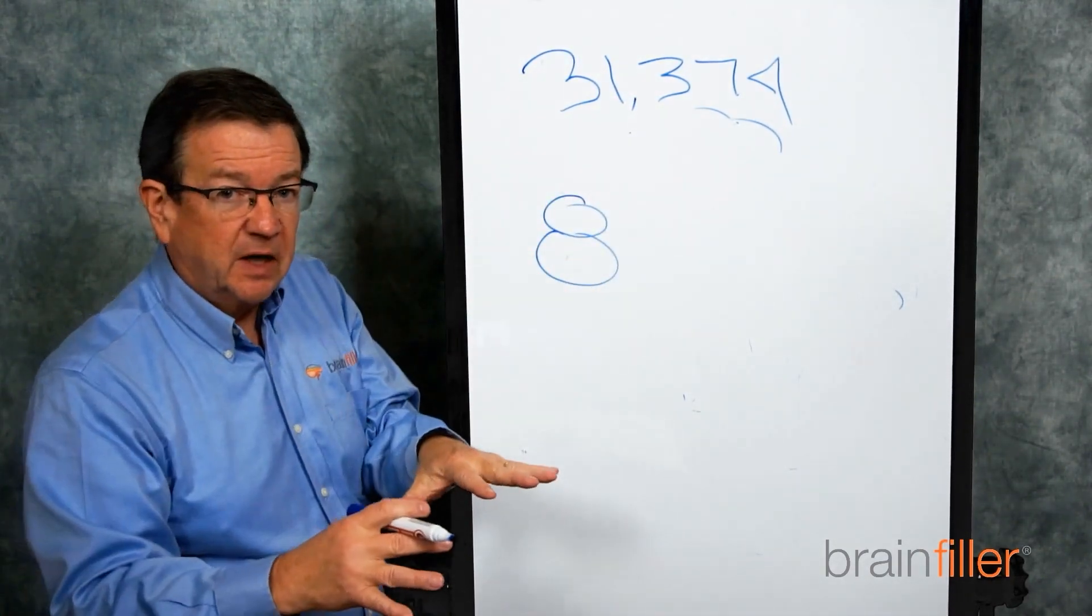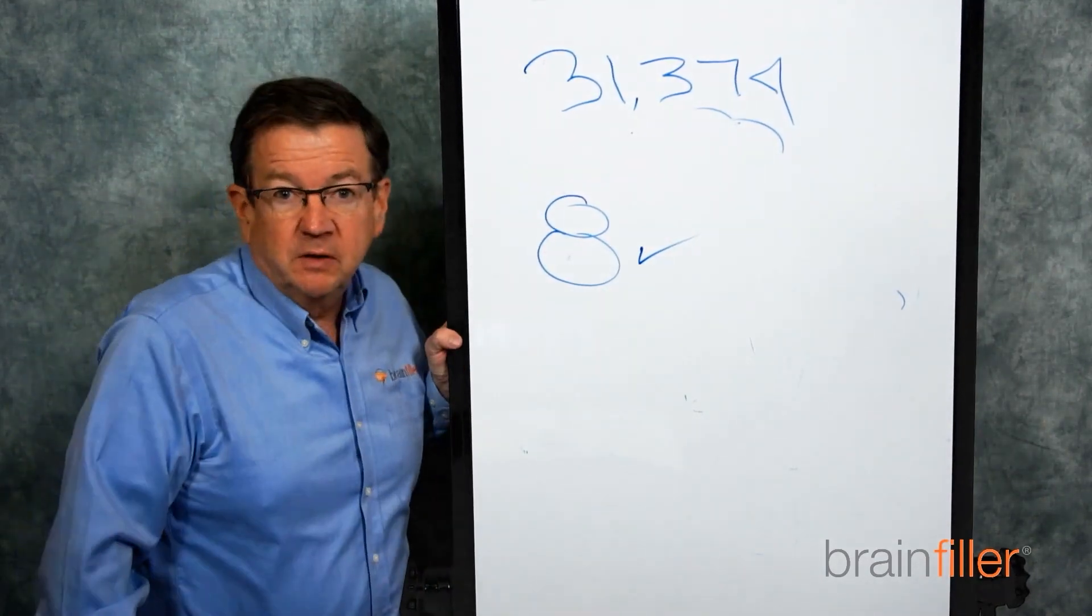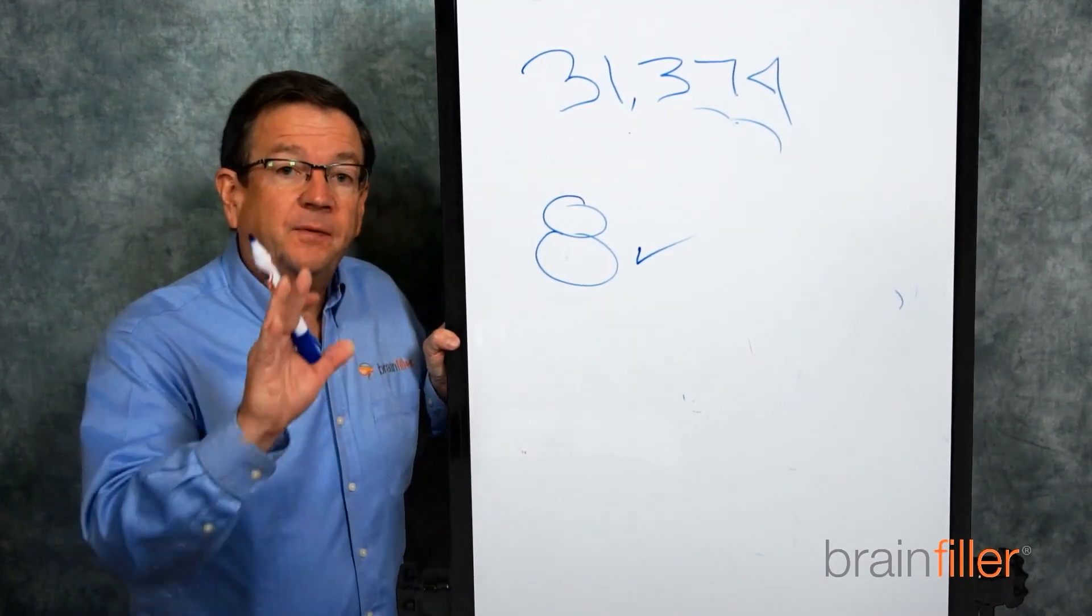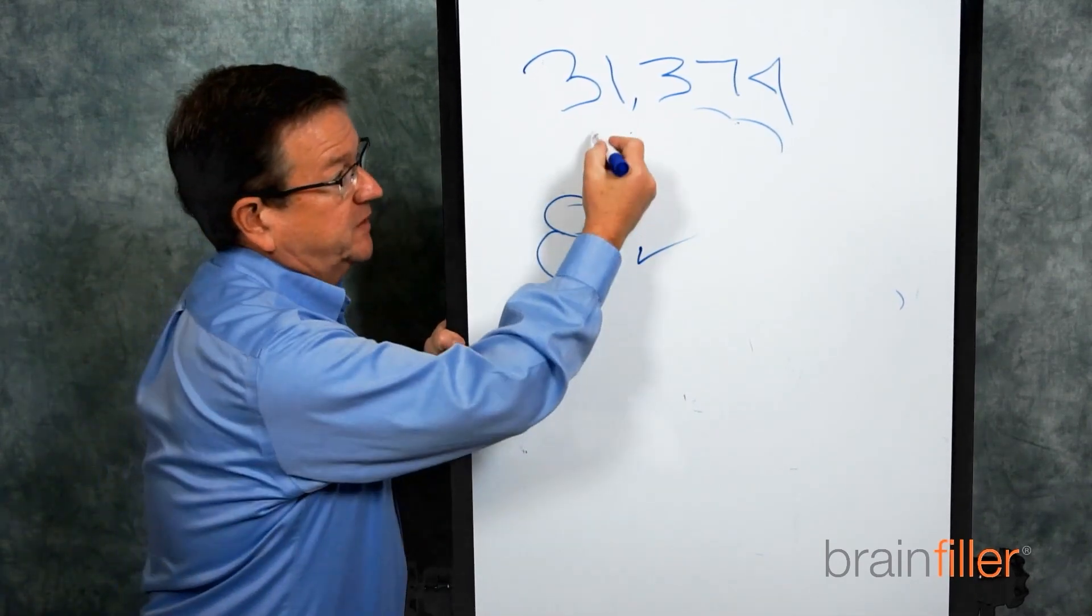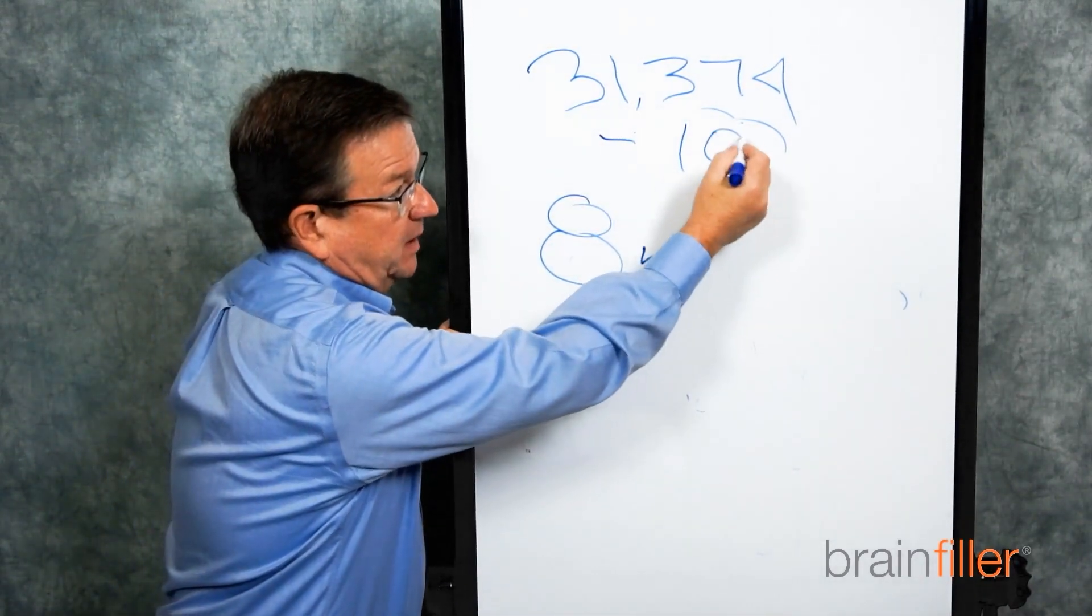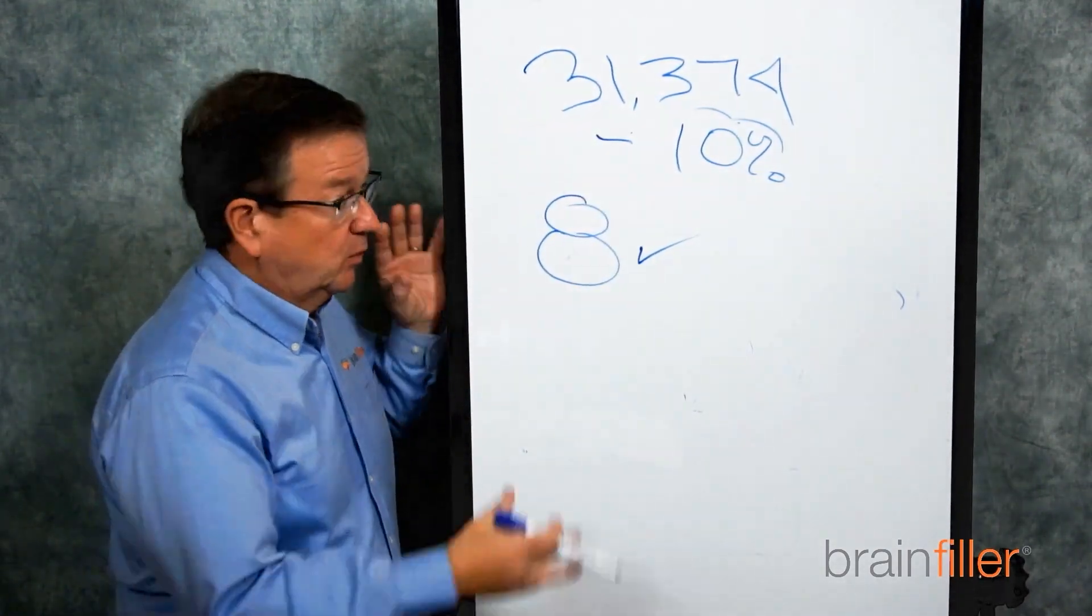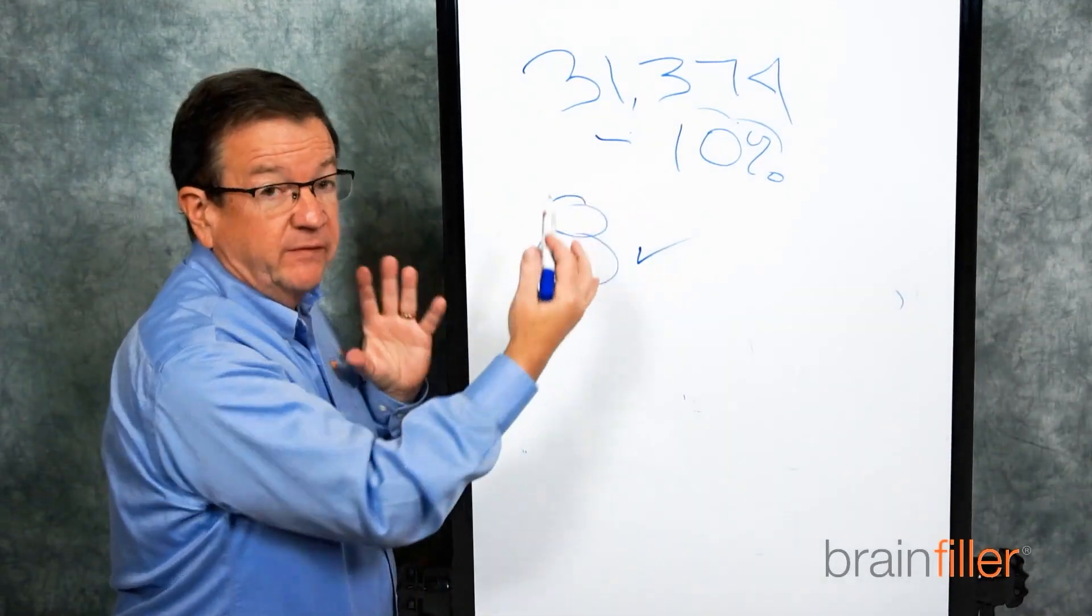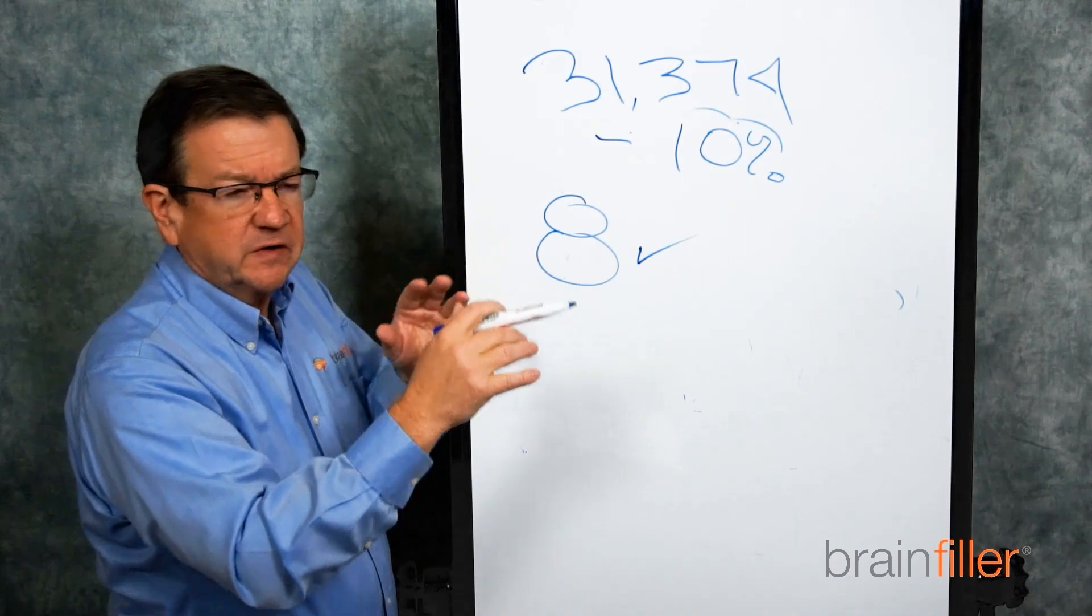You start out with 31,374, build your model, run your study, and identify all the locations where 8 calorie is going to work. That's your base case. Now, take the 31,374 and subtract maybe 10%, reduce it. So you drop it a few thousand amps. Rerun the study. It's easy to do that when you have a database, when you're using software. Just go up to the source and change it. It's real easy.